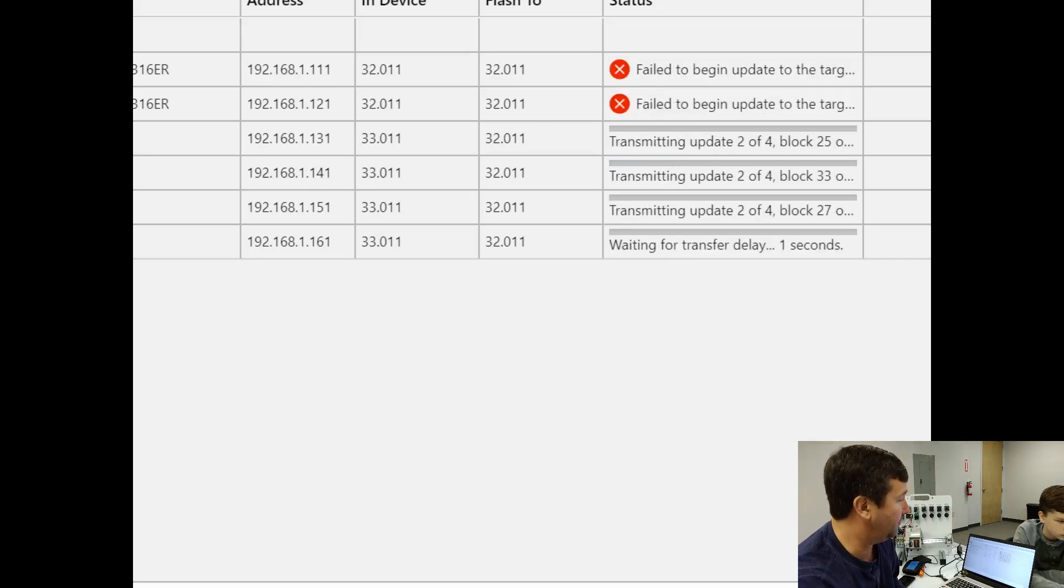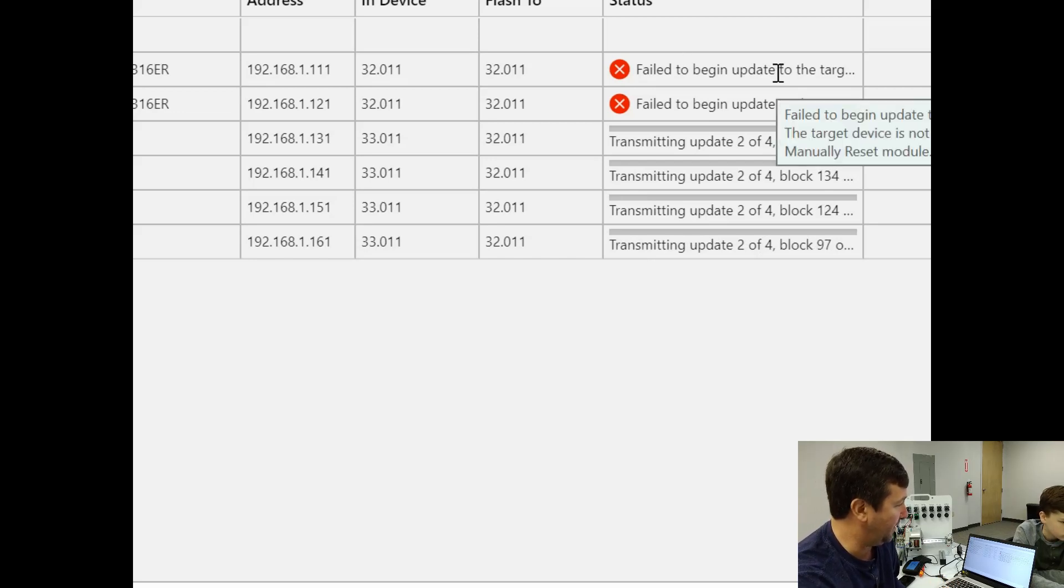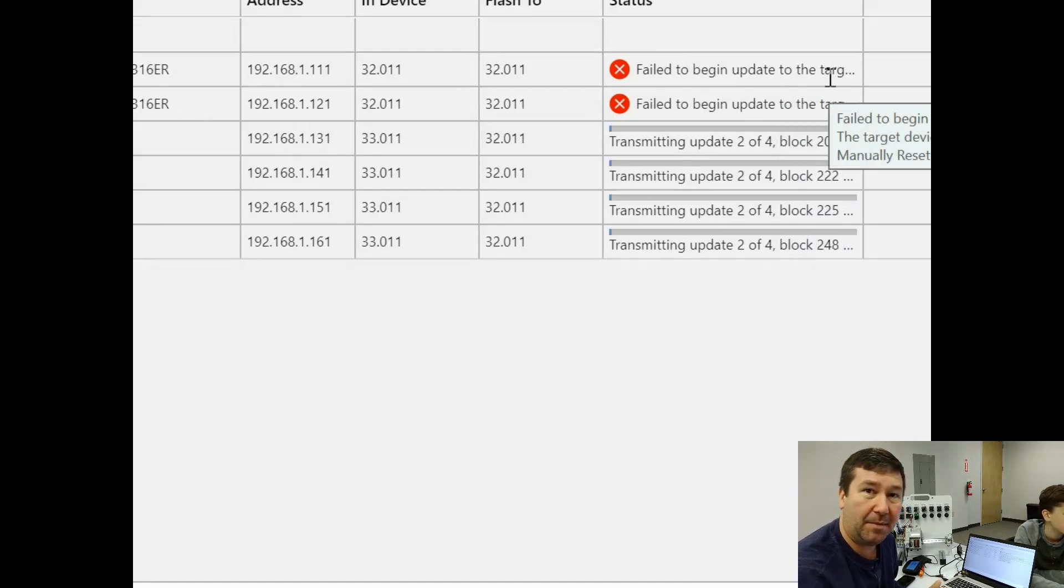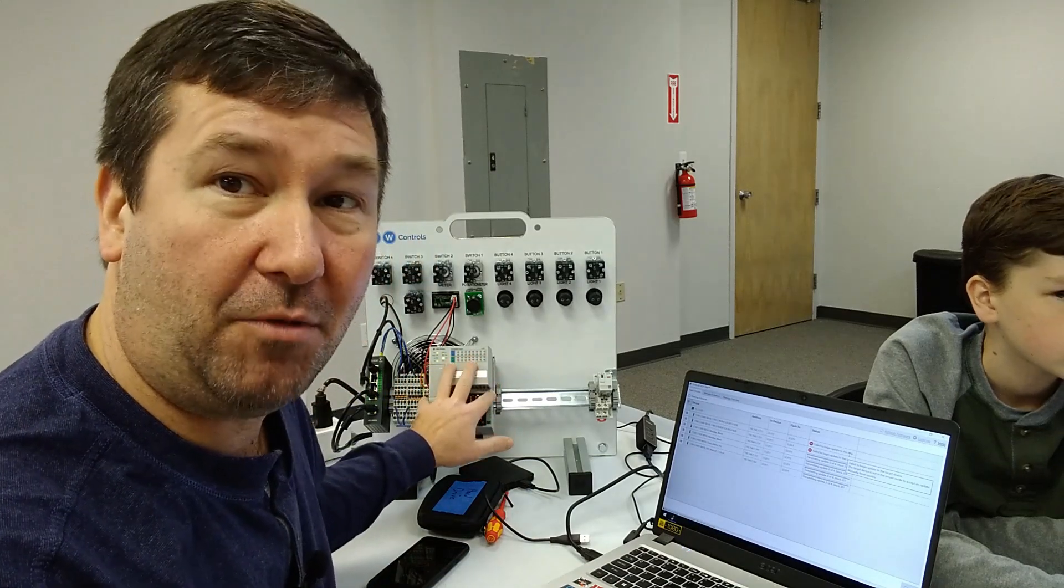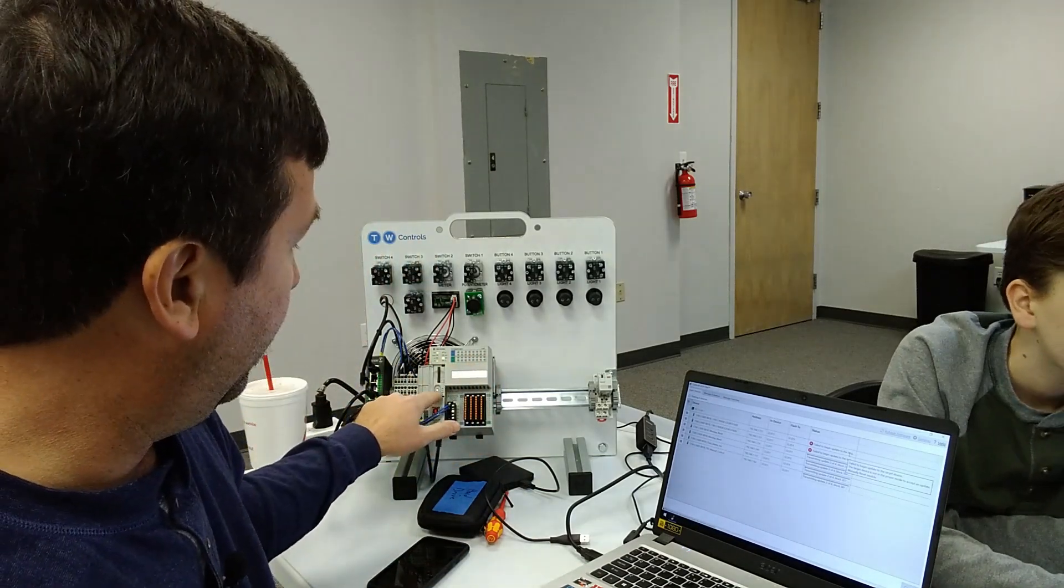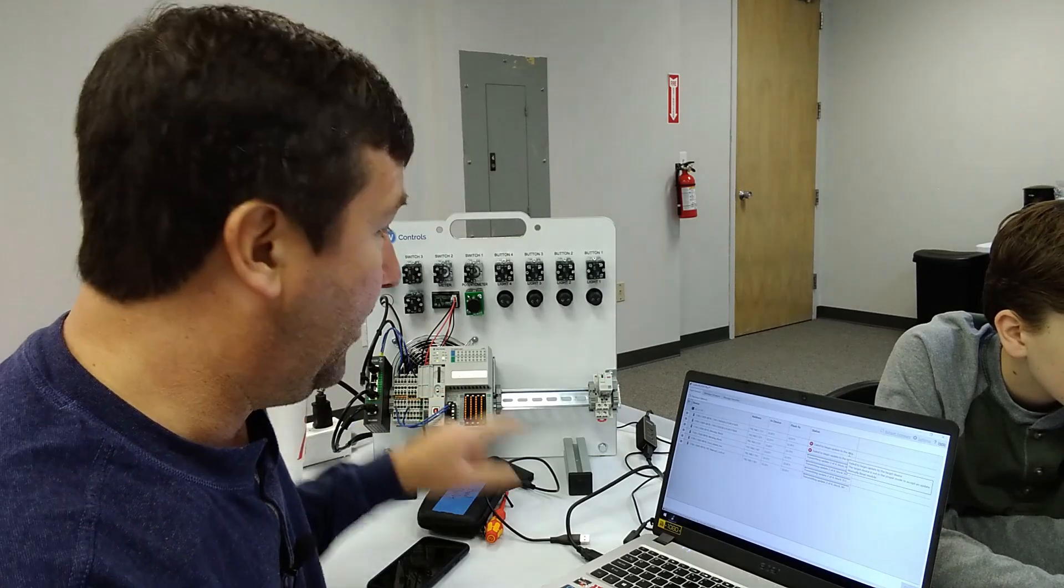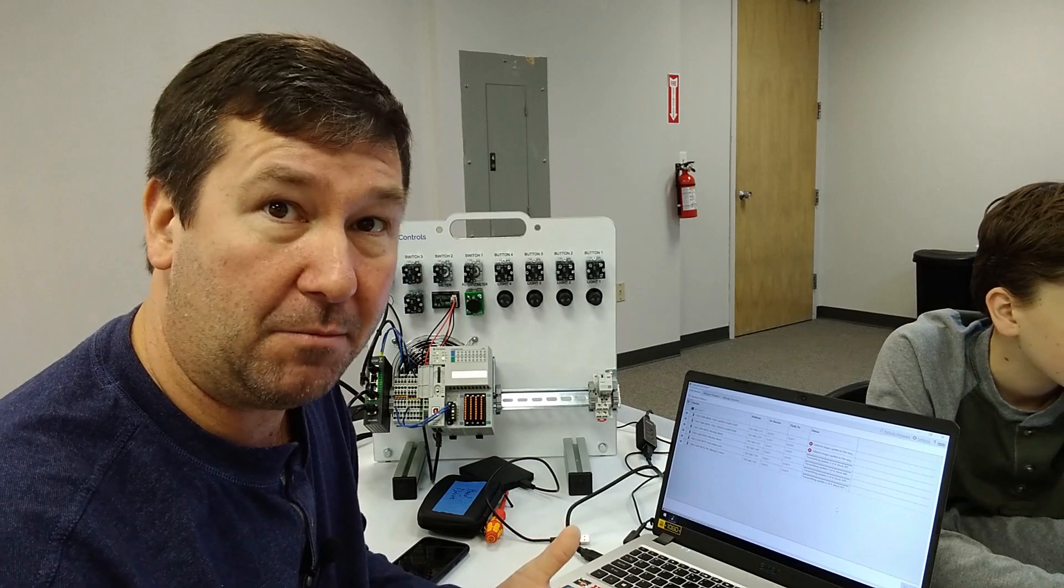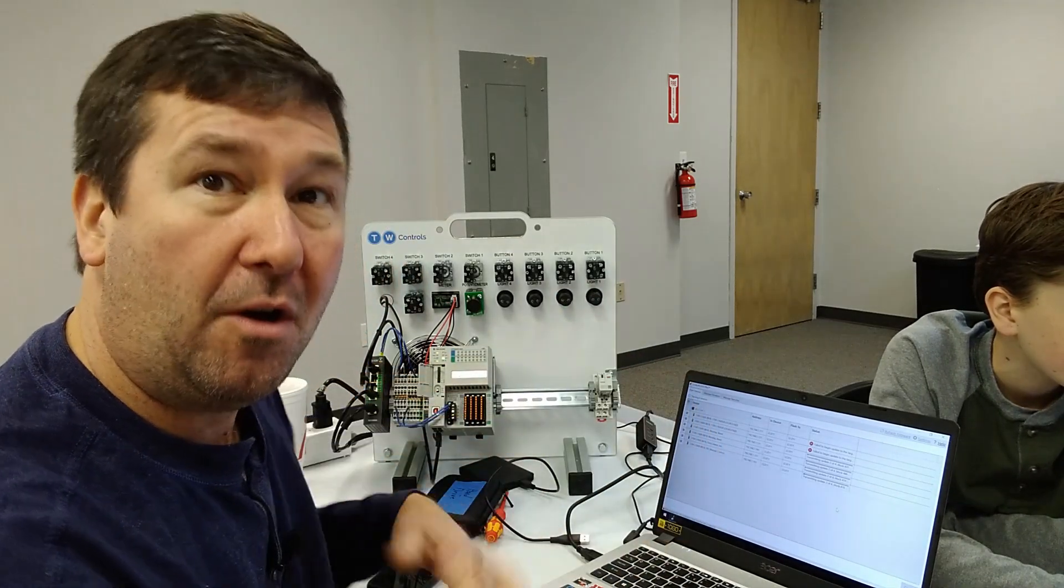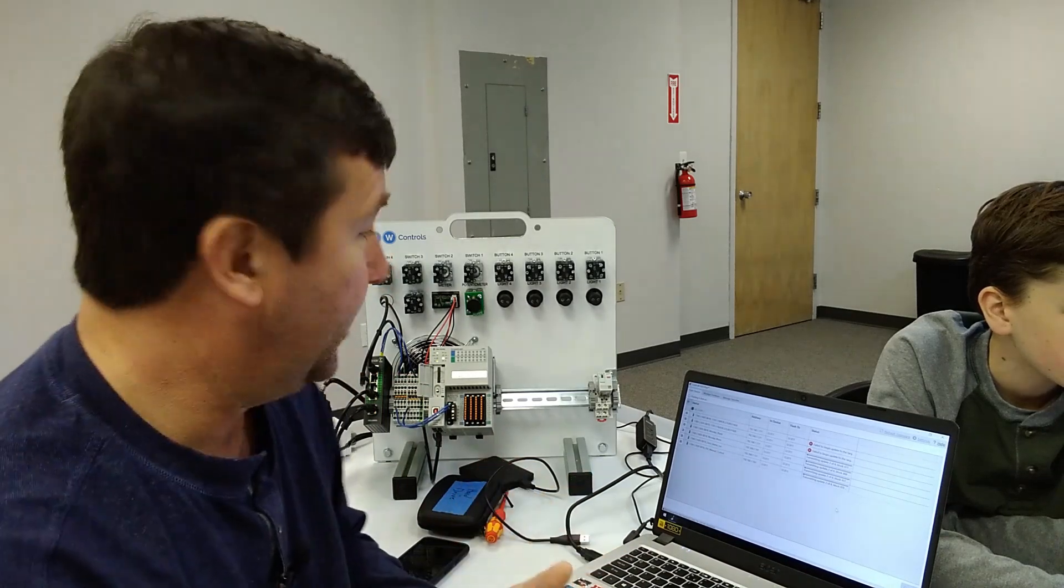And so the first two actually got failed to begin the update. And if I mouse over, it says failed to begin update to the target device. The device is not in the proper mode to accept the update manually reset module. And the issue is I have this one, this is one of them. It's in run mode right here. Actually it's in remote run. Now these four here, I still have in program mode. So to do this, your PLCs do need to be in program mode, whether they're switched to program mode or we have them in remote program.